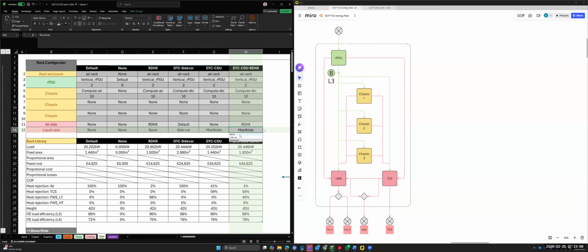So if you look at what type of equipment is configurable at the rack level for liquid, we have options of none, i.e. where all the heat's rejected on the air side, or a sidecar, which is a form of CDU but associated directly with the rack, hence defined at the rack level. So a sidecar is matched to a specific rack.